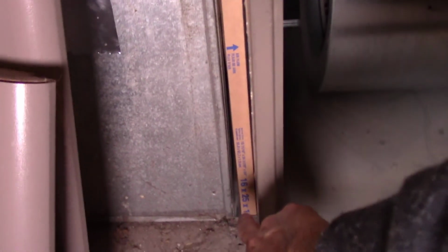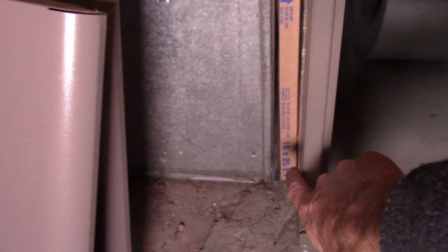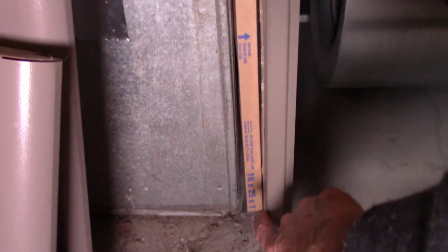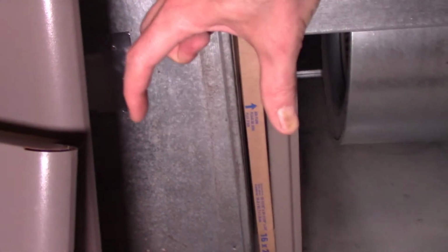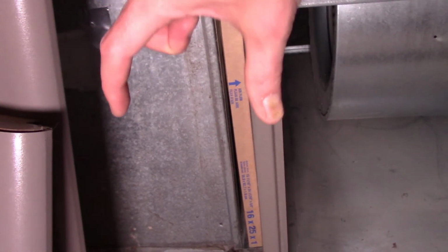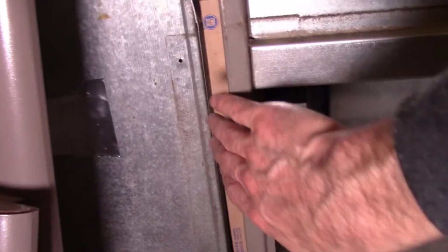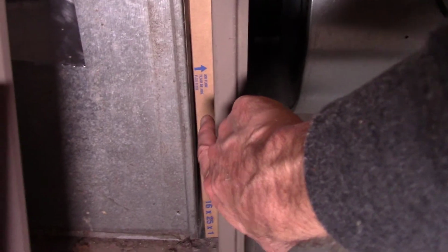You guys probably already know how to do this. Just check to see if you have the right size based on the old one. Mine's a 16 by 25 by 1. You might have one that's 1 inch, or it could be 4 inches thick, could be inside of a door, whatever. But always make sure you replace that a couple times a year. Also, they have an indicator for airflow. You can see that the airflow is going into the furnace, which makes sense, right?